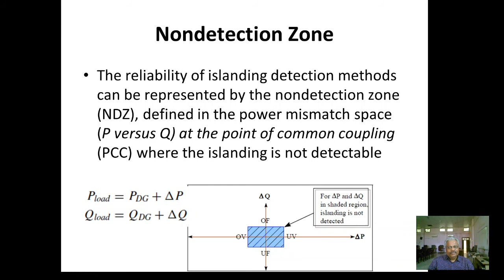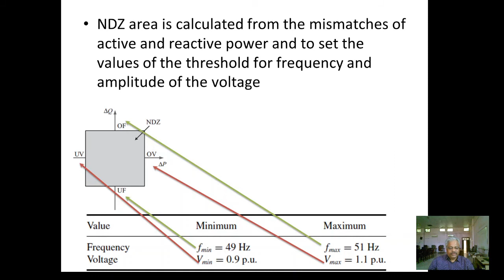That's why the NDZ situation is shown here again. This is 49 hertz, this is 51 hertz, this is 0.9 per unit, this is 1.1 per unit voltage. If things are within this region and the circuit breaker opens, then there will be a non-detection zone and your protection will fail. What this means is that over voltage, under voltage, and over frequency, under frequency protection is not sufficient, due to, of course, the non-detection zone.